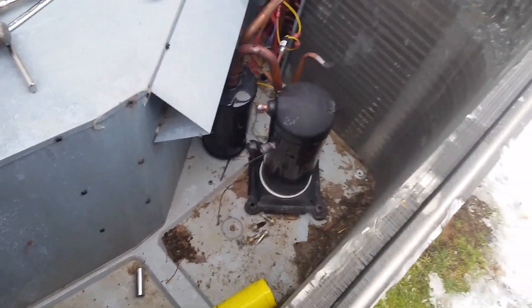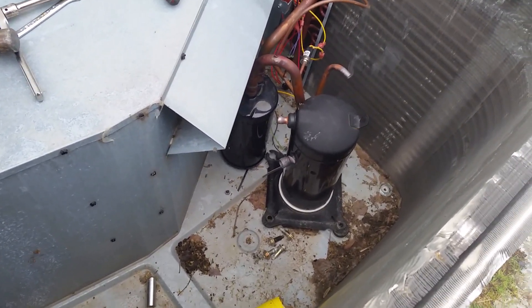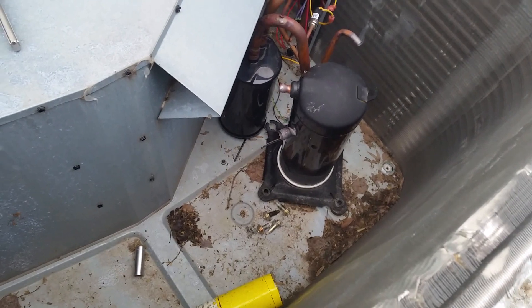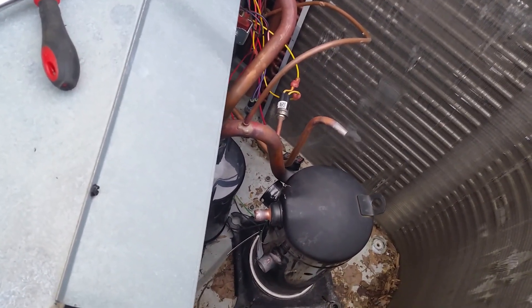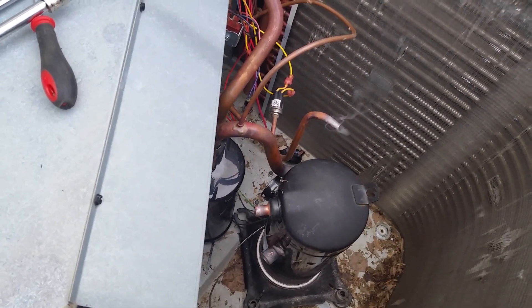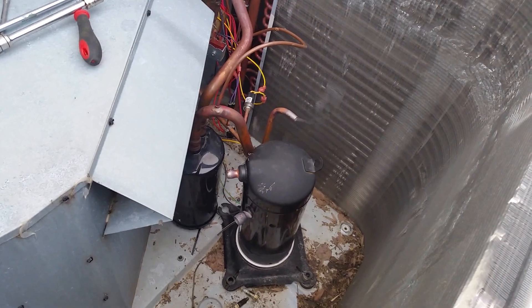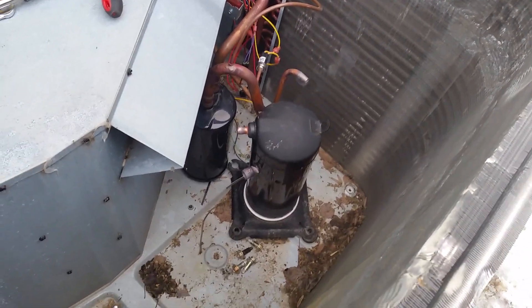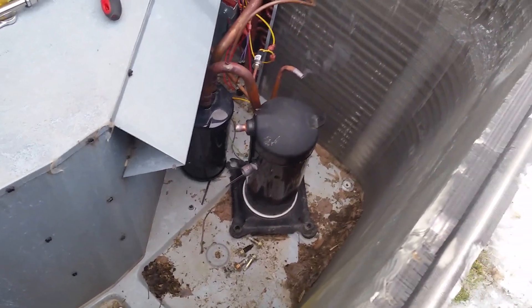So we flushed it out and unbrazed the connections. And you can see we even pushed it through with nitrogen and we're still getting a little bit of gas coming out. We'll wait a little bit and then push some more nitrogen through to get all that gas out, and then I'll take the old compressor out and put the new one in.